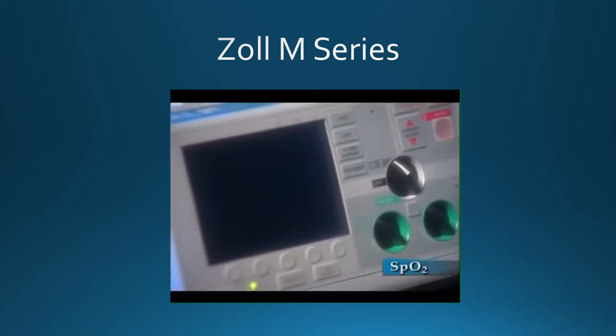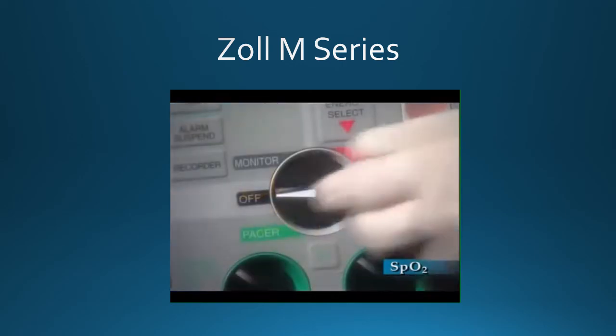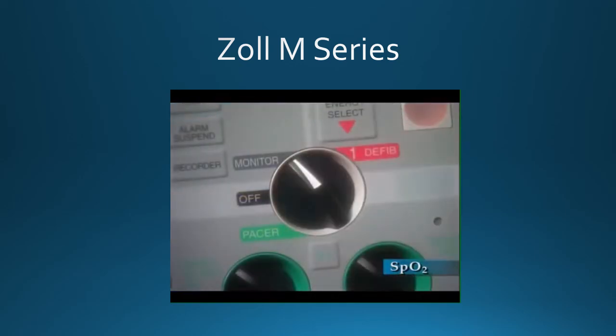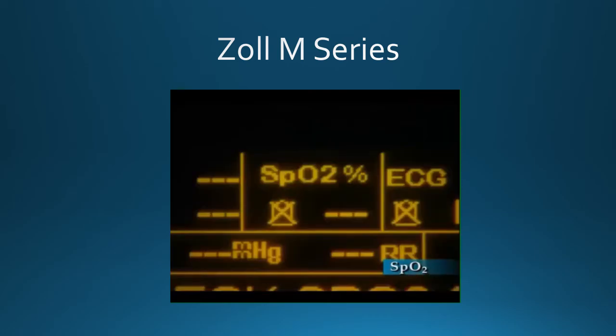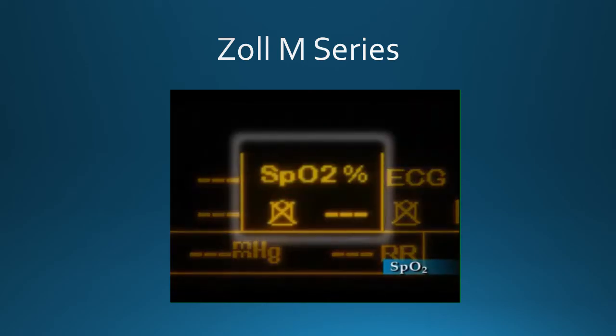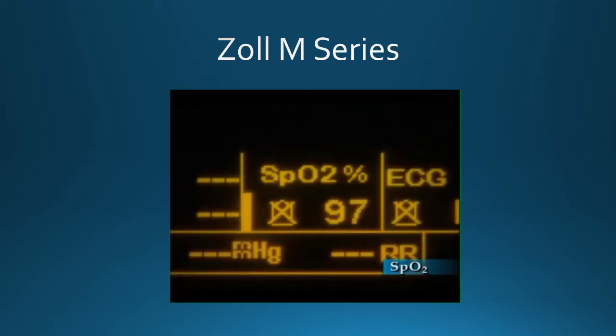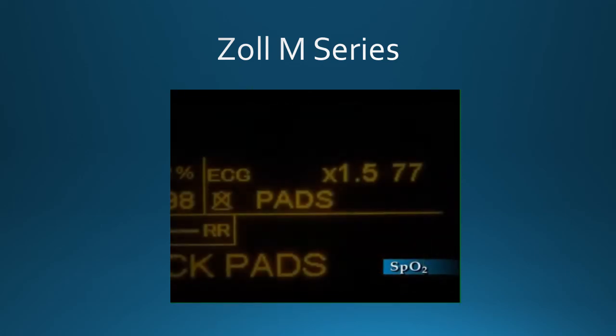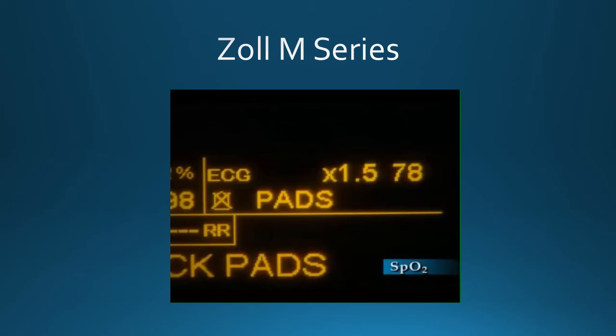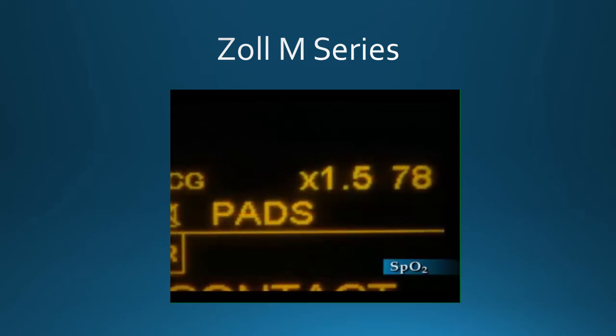Turn the M-Series selector switch to on if you are using an AED, or to monitor for advisory and manual devices. A dashed line will be displayed in the SPO2 field until a pulse is detected. Once the measurement has been established, the saturation values will be displayed in the numeric window. If ECG leads or pads are not attached, the patient's pulse rate, as measured by the SPO2 sensor, will be displayed as the heart rate in the ECG field.